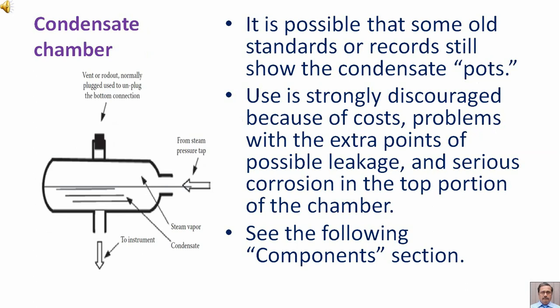It is possible that some old standards or records still show the condensate pots. Use is strongly discouraged because of the costs, problems with the extra points of possible leakage, and serious corrosion in the top portion of the chamber. See the following components section.